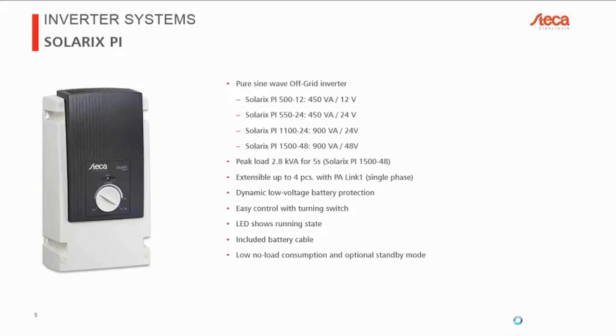of loads you're powering. Just for your information, if you're powering things like AC pumps or AC refrigerators, anything that has a motor, a compressor, something like that inside, you will need to deal with peaks at a very minimum of 2. So if you have, let's say, a 500-watt motor, you will have to deal with at least 1 kilowatt while it's starting up. But that's a very, very small number. To be honest, the vast majority use 5 to 10 times their nominal power at the peak. So this is something you really need to keep in mind.